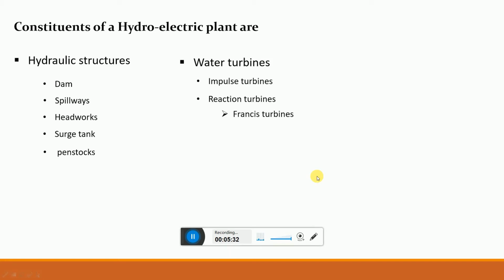So the Kaplan turbine is used for low heads and larger quantities of water. It is similar to the Francis turbine, except the runner of the Kaplan turbine receives water generally radially inwards through the regulating gates all around the sides. So the reaction force drives the turbine. So these are all about water turbines.